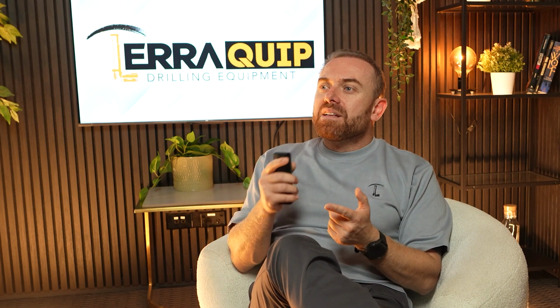So what are some of the most frequent issues, let's say, that we get calls about when it comes to Marini Mast Attachments? They can vary from not connecting the right electrical cable, not being the right voltage, as I said, or just connecting one of the batteries instead of both of them. So if the Mast Attachment PLC gets the wrong power supply, it acts all crazy and confusing. And this is the confusing part for everyone, because sometimes, as I said, it does work, and it opens the valves completely, so the mast is somewhat operational, but then sometimes it acts all crazy. You can't execute any other functions.